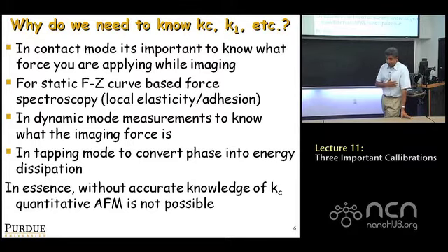This is one of the things you often see: when people take a contact mode image, I ask them, well, what force did you apply when you took that image? Most people will say, I applied 1 volt of force. Is 1 volt a unit of force? It doesn't make sense. If you go through the calibration process, convert volts to nanometers of cantilever deflection, and multiply cantilever deflection by the calibrated stiffness, then you know the force in nanonewtons.